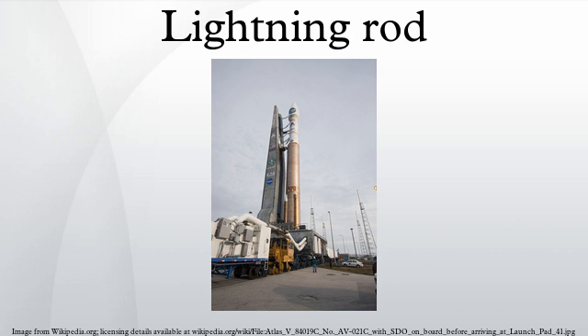The majority of lightning protection systems in use today are of the traditional Franklin design. The fundamental principle used in Franklin-type lightning protection systems is to provide a sufficiently low impedance path for the lightning to travel through to reach ground without damaging the building. This is accomplished by surrounding the building in a kind of Faraday cage. A system of lightning protection conductors and lightning rods are installed on the roof of the building to intercept any lightning before it strikes the building.